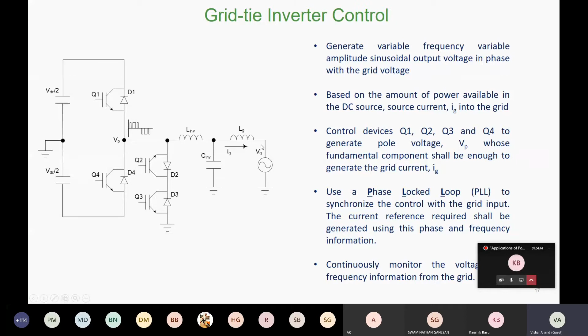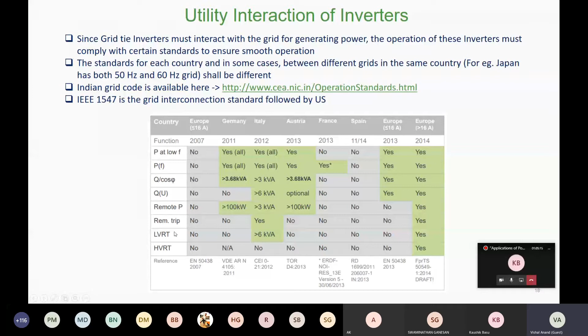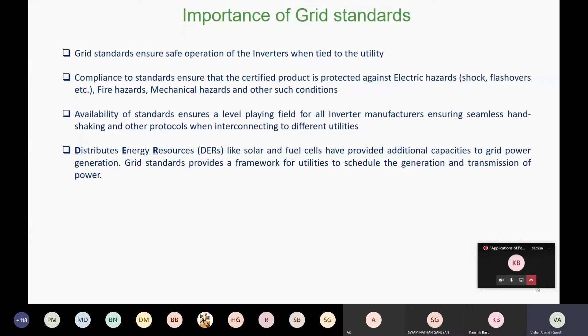Now let's look at the utility interaction. Since we are feeding power into the utility, the grid tie inverter must always keep looking at the voltage and frequency and ensure that they are within the required limits. Each country has its own grid standards, and it's imperative that the inverter follows the country's grid code. The Indian grid code is available here, and these are the codes of different countries and their requirements in terms of voltage, frequency, and power factor. The grid standards are very important. They ensure that the inverters operate safely, comply with all the other requirements, and that there are no hazards in operating the inverter.